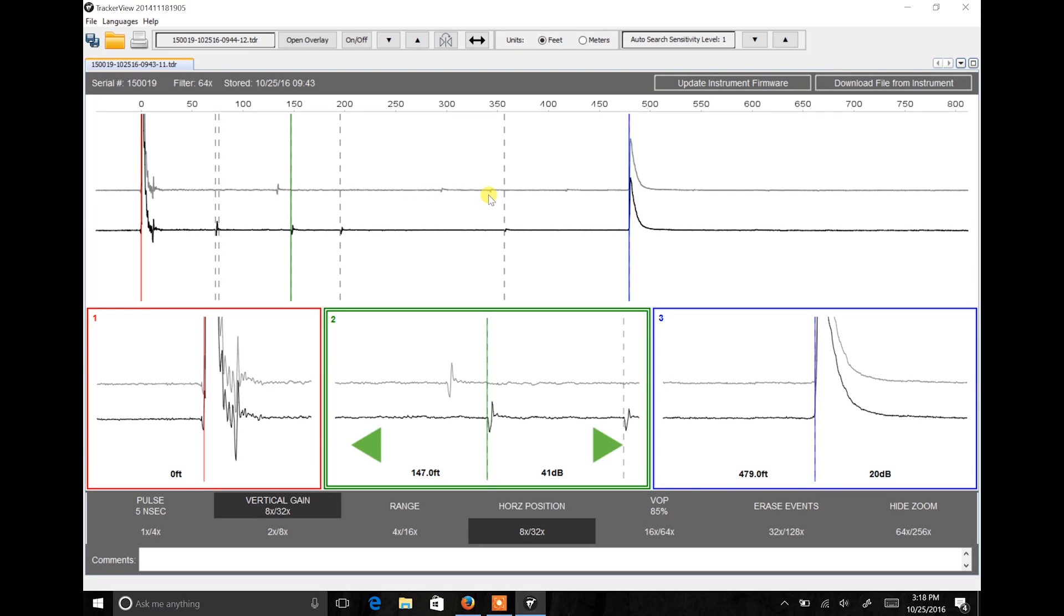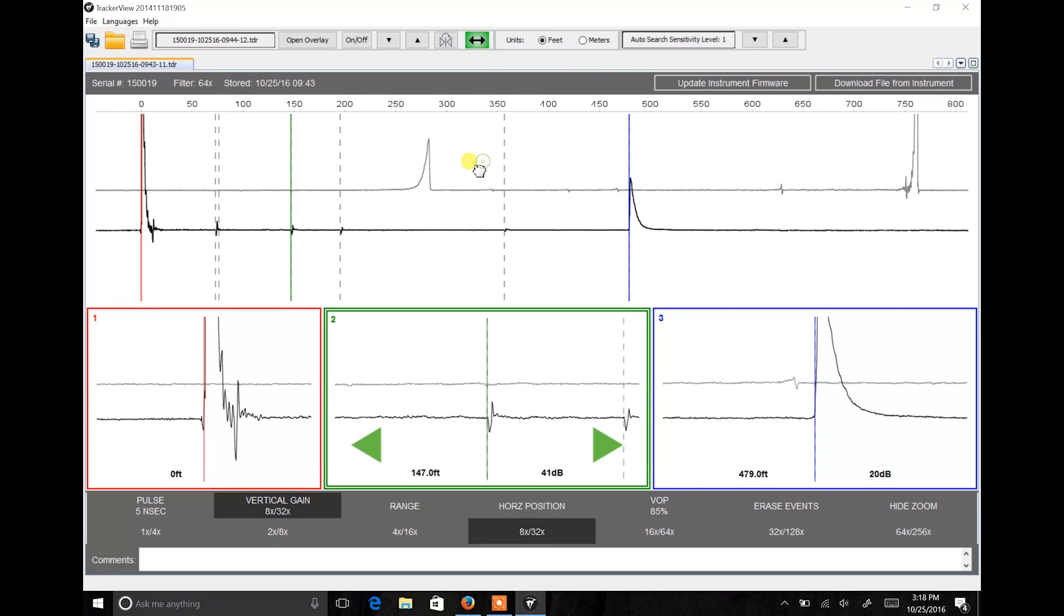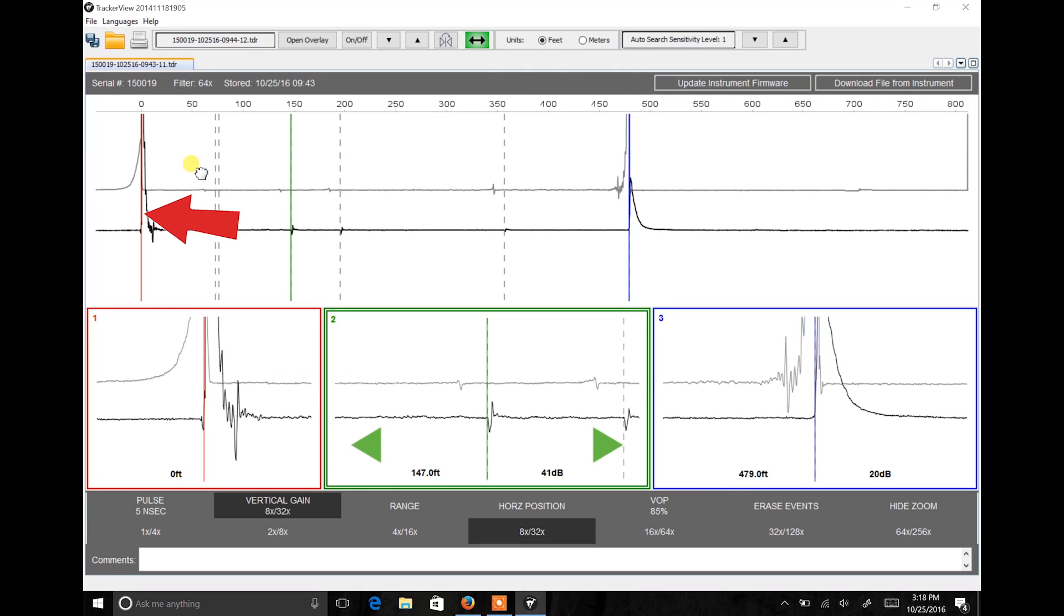In this example, we've got the same piece of cable shot from both ends. So it's helpful to mirror the overlay and then adjust it left to right so that the events align. I'd like to roughly adjust the end of the cable of the overlay with the outgoing pulse of the primary waveform.